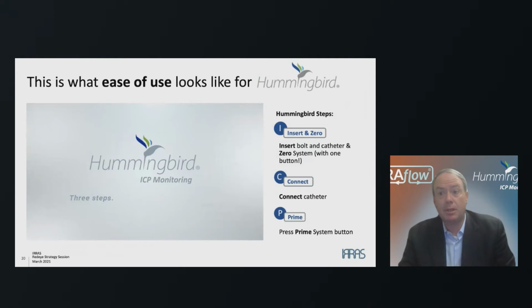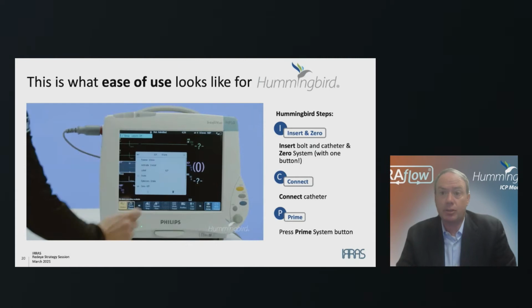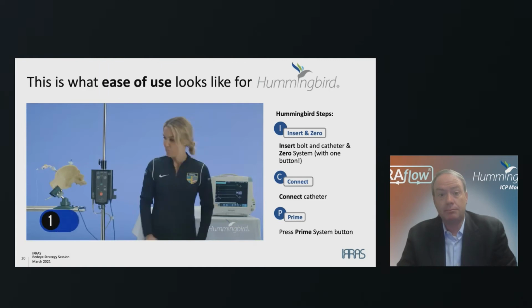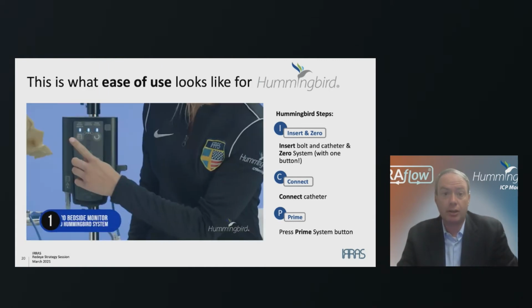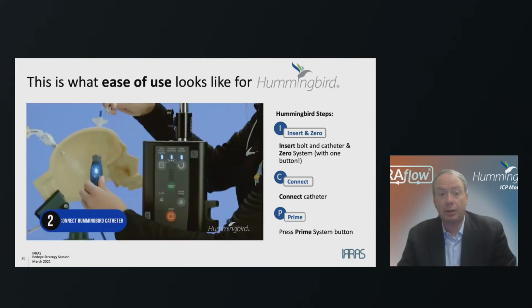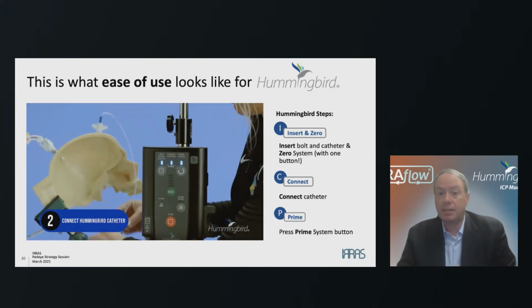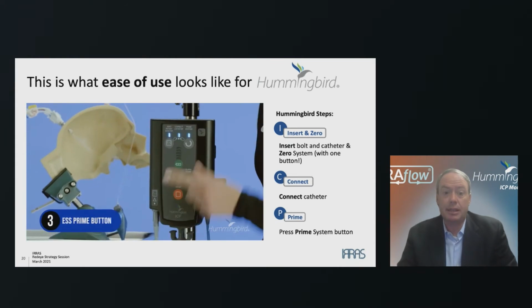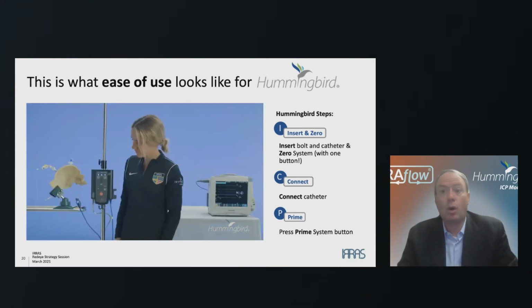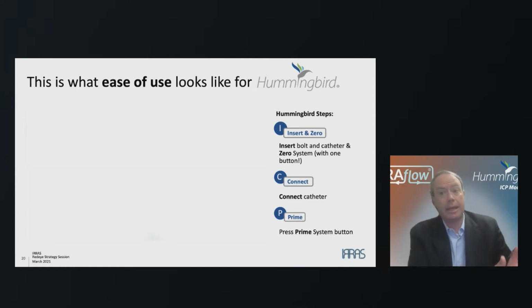Whereas with Hummingbird, we are looking at 3 steps. What you see in the video here truly is all of the setup that is required for the Hummingbird system. We zero the system on the patient's monitor in their ICU room, connect the catheter, and then press a button to prime the system. Those 3 steps, in just a matter of seconds, are what's required to set up the Hummingbird system. That combination of accuracy and ease of use is something we are building upon as we roll the system out in a more broad fashion.